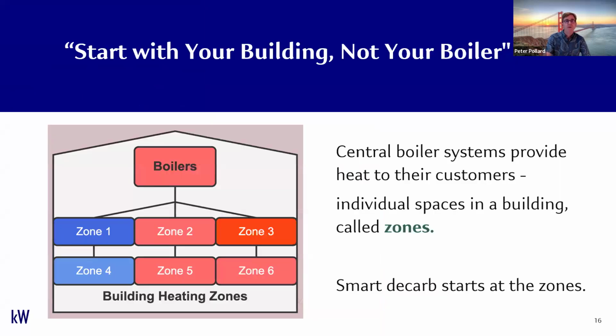So we want to start with the building, not your boiler. I like to think of each zone—a fancy word for individual spaces in a building served by the heating system. Those are really the customers for the central boiler system. This whole approach is about minimizing peak demands and high temperature demands in certain critical zones throughout your building—getting really familiar with those customers, as it were, in a given building.